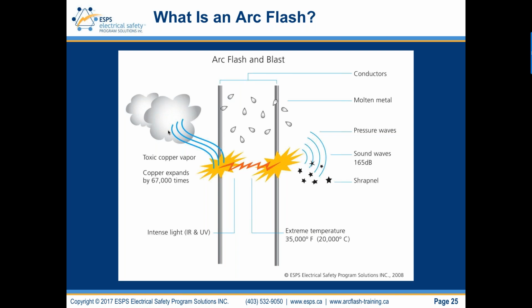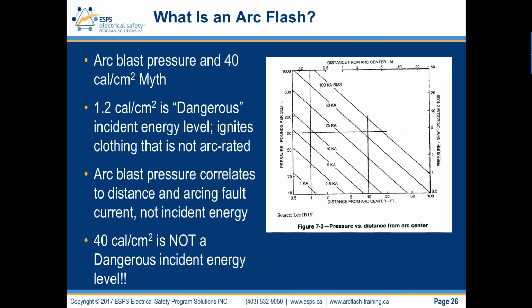We get molten metal and shrapnel. We get toxic vapor. Copper vaporizes at 2,400 degrees Celsius and expands 67,000 times. It gives us that pressure. And we get UV and IR light. So we've got these effects that are caused by an arc flash, and some we can manage with PPE, some there is no PPE. And it's a matter of understanding that and also understanding that those effects don't necessarily have a high probability of injury or damage to health.